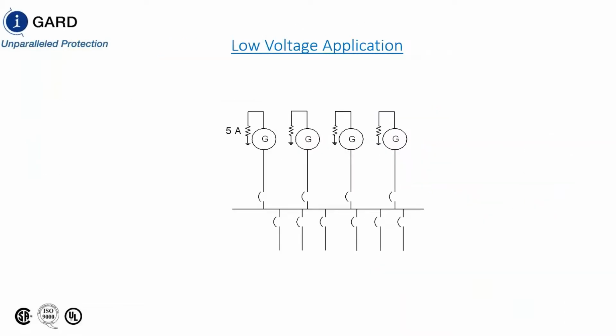But what we've done is we've taken that concept of a medium voltage bus connected generator and applied it to low voltage. One of our customers in Canada came to us and said they have a system where they had 10 generators running, and if you have a 5 amp resistor on each generator, and you get a ground fault current, your current is going to be limited to 50 amps.